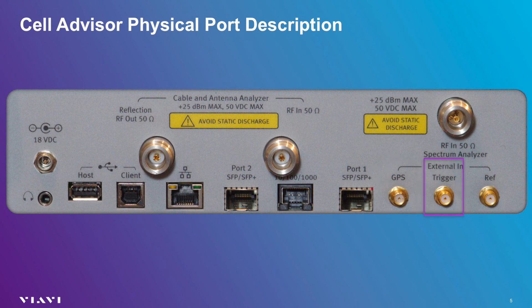Located to the right of the GPS port is the trigger port. The trigger port connects external signals that are used to start or trigger internal measurements. The reference port is used to obtain external timing signals. External references are sometimes used when GPS signals are unavailable or when a measurement requires extreme measurement accuracy. In most circumstances, the trigger port and the reference port are not required.